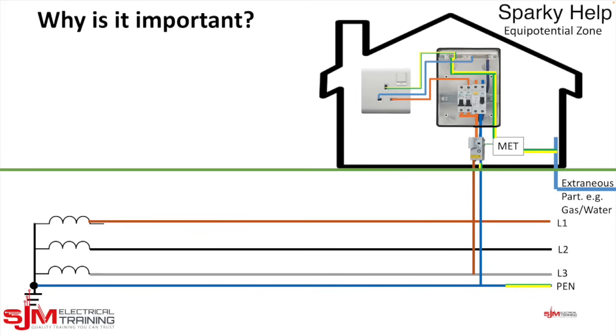And what we do is bond everything together in general, and we create something called an equipotential zone, which creates an equal voltage. Therefore, if anyone in there were to touch anything that was metalwork, be it an exposed conductive part, an extraneous conductive part, or any other part that could become live, because we've connected them together, they would all be assumed to be at 0 volts. Because there's no potential difference between them, no one would receive an electric shock, so it's not a problem. This is what we try to do to create an ADS, an automatic disconnection of supply. That's what we try to achieve within our regulations.